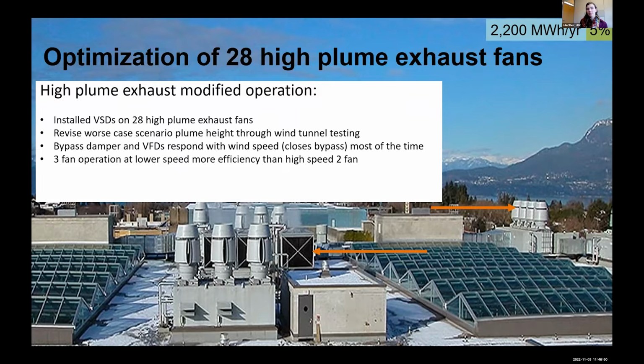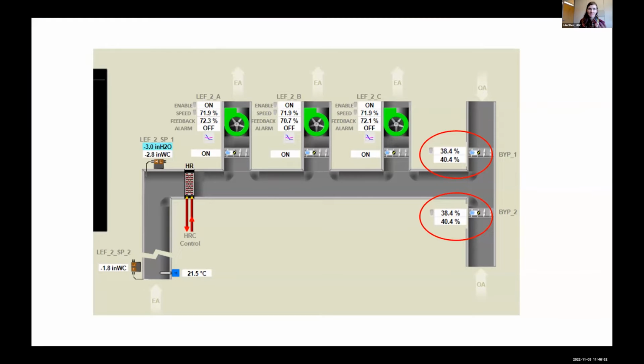And so when you look at this, this is a BMS graphic of an exhaust fan system, and how it works is that you've got air coming in, exhaust air from the laboratory that's being exhausted out of these exhaust air, and then you also have outdoor air coming in that mixes and essentially gets exhausted out. And so what we are able to do is basically close these bypass dampers, and then that in turn reduces the speed of the variable speed drive, which has substantial savings.